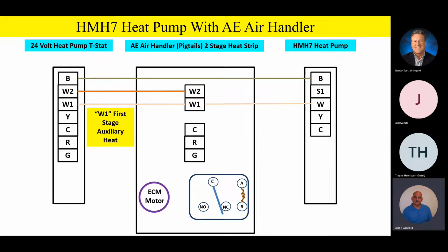W1 is your first stage auxiliary heat, or your first stage heat strip. And you'll notice that W1 goes from the thermostat to the indoor unit and then also outside. Now, it should be noted that during defrost operation, the outdoor unit will energize the W terminal outside to bring on that first stage of heat strip during defrost. That's why we have to have that W wire going all the way outside as well, so we can have one stage of the heat strip coming on when we go into defrost.